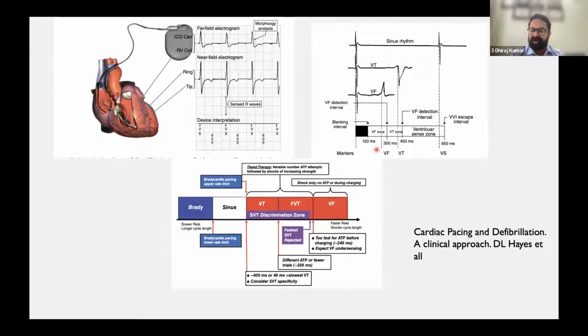Now, it is very important that the device understands that after a ventricular sensed event, within the first 120 milliseconds, any event that you get is often a blanking, often non-physiological, and therefore it goes into the blanking zone. After that, from 120 milliseconds to 300 milliseconds, if there is any event which is sensed, then it is going into the ventricular fibrillation zone. And of course, these zones can be programmed. From 300 to maybe 450 or 500, you can have any event in the ventricular tachycardia zone. And beyond a rate of 100, that is 600 milliseconds, it's a sensed zone, ventricular sensed zone.